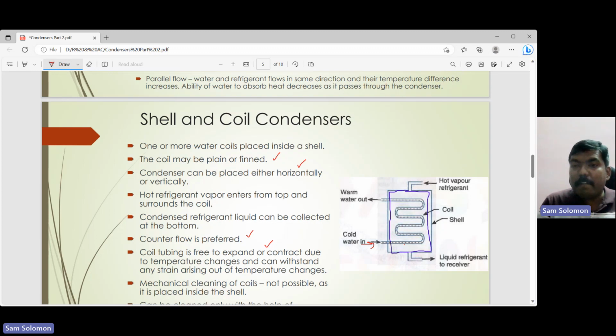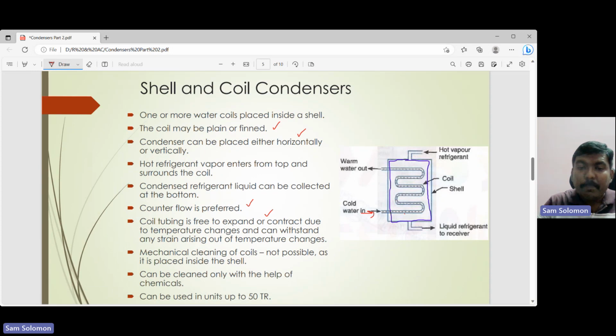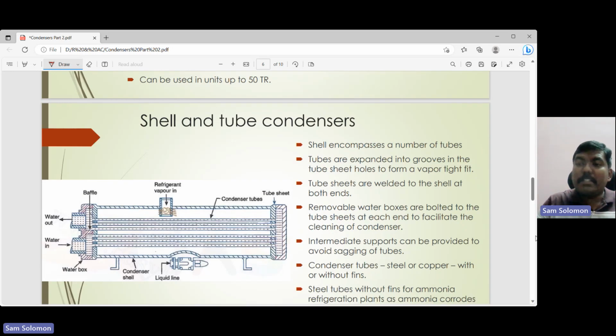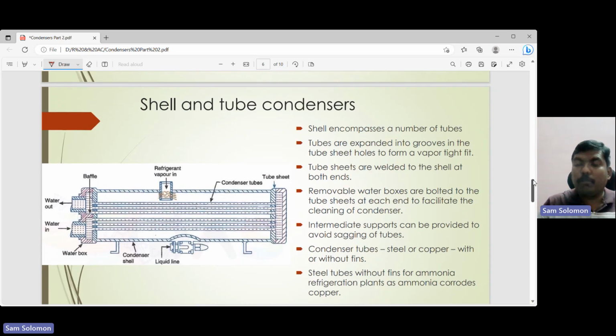The only disadvantage is this coil that is placed inside the shell. If it needs to be cleaned, it cannot be done manually. You can't open it and assemble it again and again, because it will be welded together. So it's not possible to disassemble the system easily. What you should do is use chemicals to clean the coil inside the shell. So that is one of the major disadvantages here. It can be cleaned only with the help of chemicals. And it can be used only in units up to 50 ton of refrigeration. So that is your shell and coil water cooled condenser.